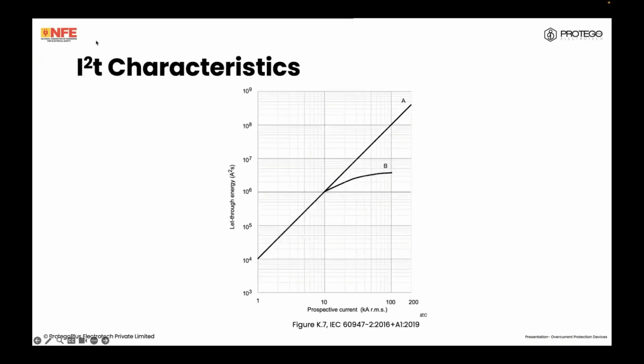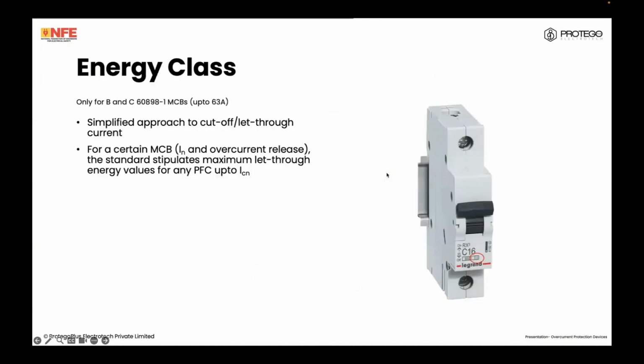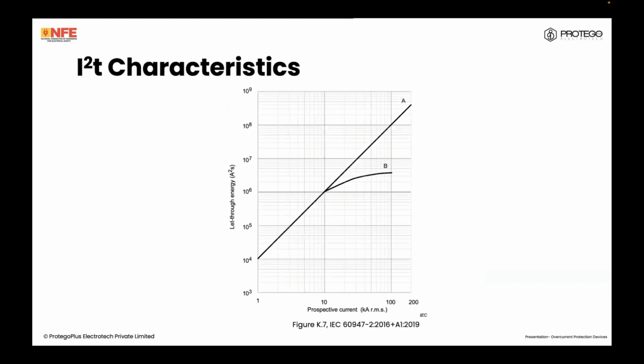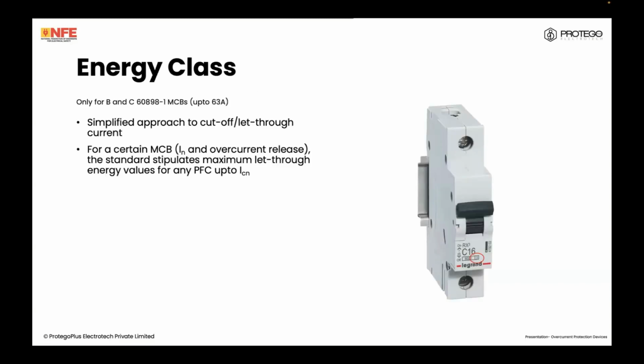Same thing for let through energy. I squared T is just a term used to describe specific let through energy. It is used for comparisons of the thermal stresses the cables are under. So again, A here is without current limiting or without the protective device. How much of a prospective current is there? That much of a let through energy is there. Once you introduce the OCPD, it is limiting the amount of fault current in there, and therefore the let through energy, which will define the amount of thermal stress. We'll look into this and calculating and coordinating this with the cable a little later.